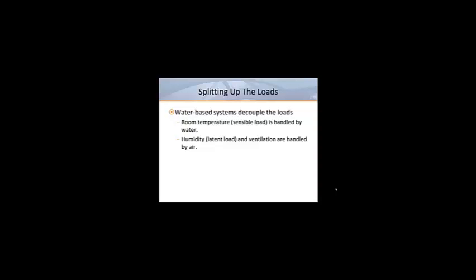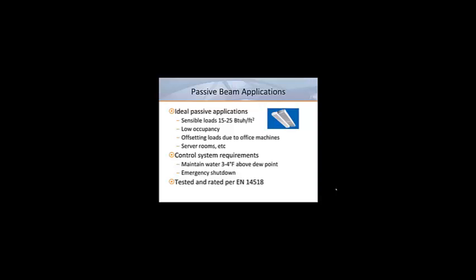Now that we know what passive and active beams are, let's take a look at the best practices and applications for both. Passive beams are best suited for handling spaces where the sensible loads range from 15 to 25 BTUs per hour per square foot. They're typically used to provide additional cooling to offset loads created by internal heat sources like office machines. For this reason, they are often found in low occupancy spaces like server rooms. Supply water temperature should be maintained 3 to 4 degrees Fahrenheit above the room dew point to prevent the possibility of condensation. In addition, the control system must be designed to automatically shut down water flow to the beams in the event that windows or outside doors are left open allowing excessive outdoor air infiltration. Currently, the passive beams are tested and performance rated in accordance with a European standard called EN 14518.